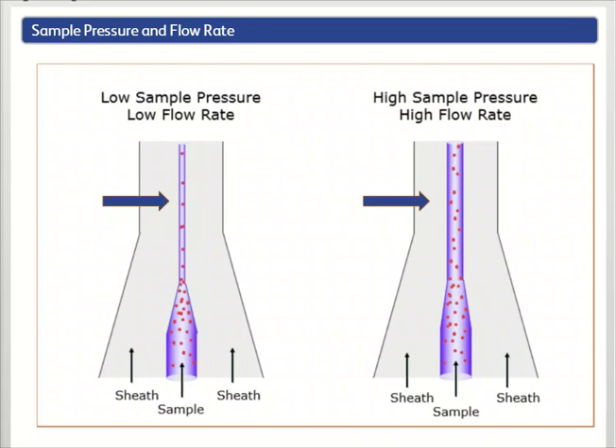With a wider sample core, some cells could pass through the laser beam off-center and intercept the laser beam at a less than optimal excitation intensity. Thus, higher sample pressure can decrease data resolution.